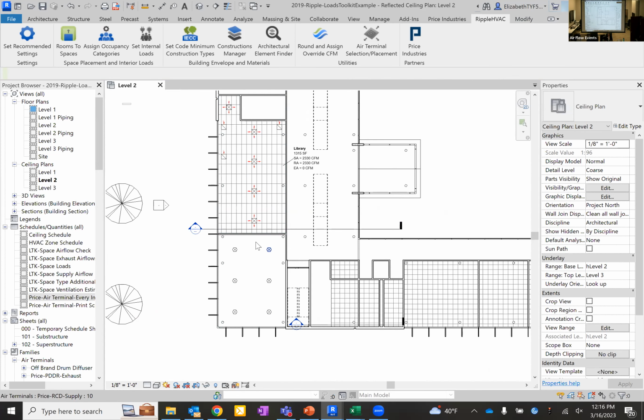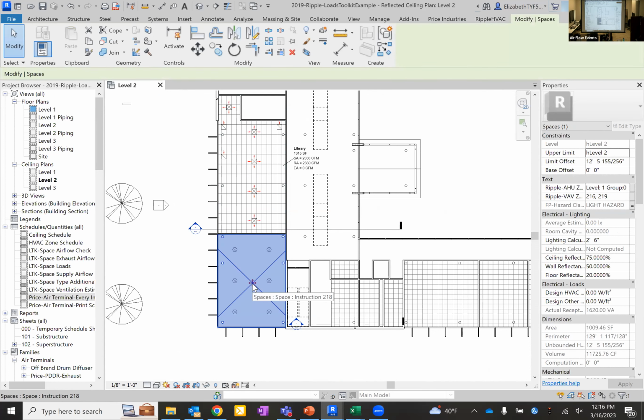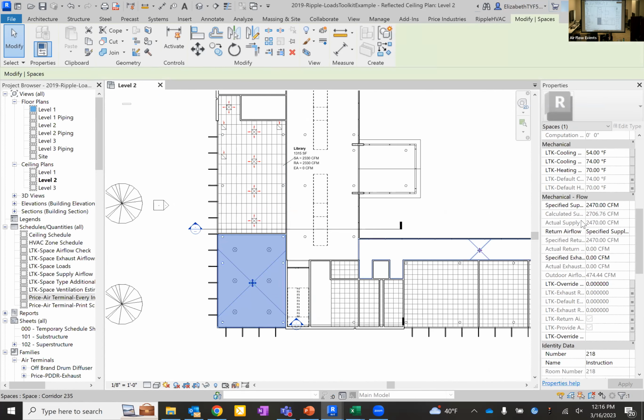Now, what is the tool actually requiring to make this happen? It requires 2 things. In your Revit model, all of the rooms need to be defined as spaces. So this room right here is actually denoted as a space in Revit. The second requirement is airflows. It requires your supply, return, and or exhaust airflow to be established for each space. So then the tool can take that space, its requirements, and choose the number of diffusers and place them.